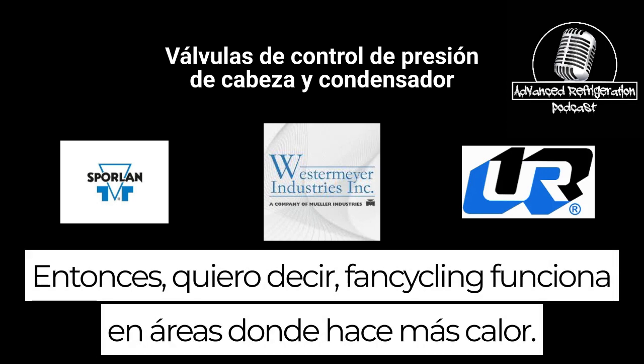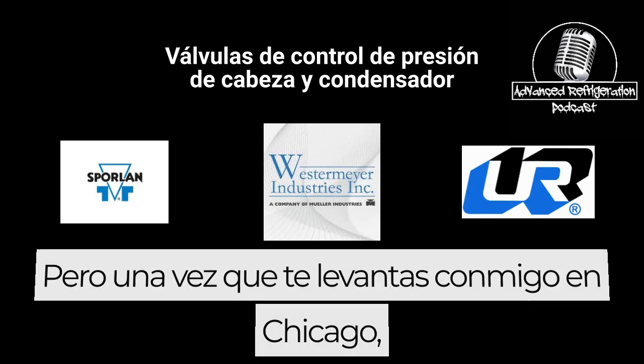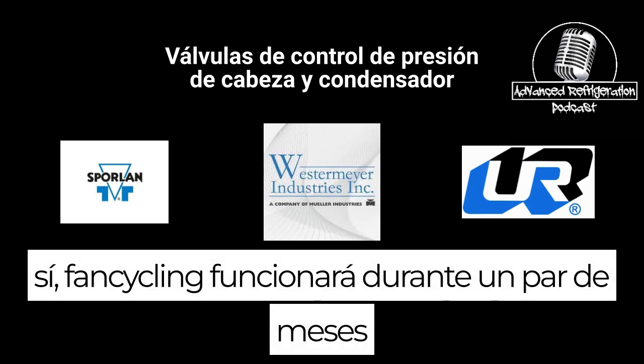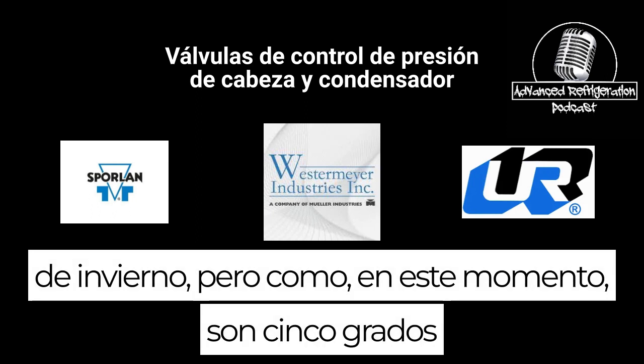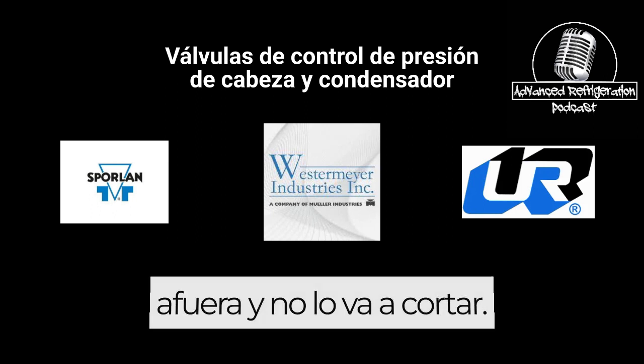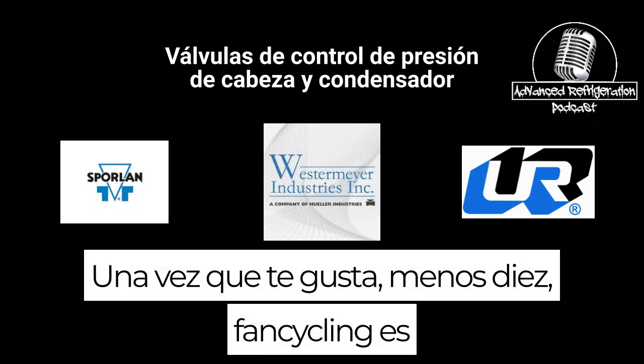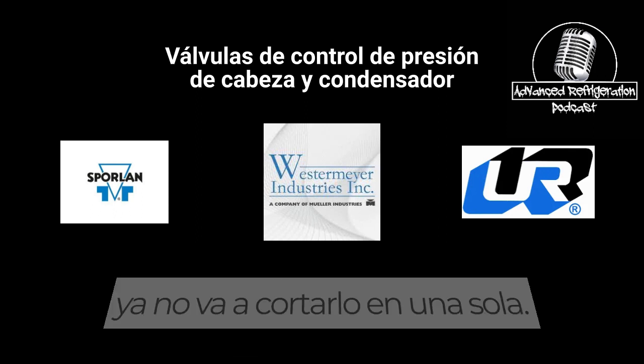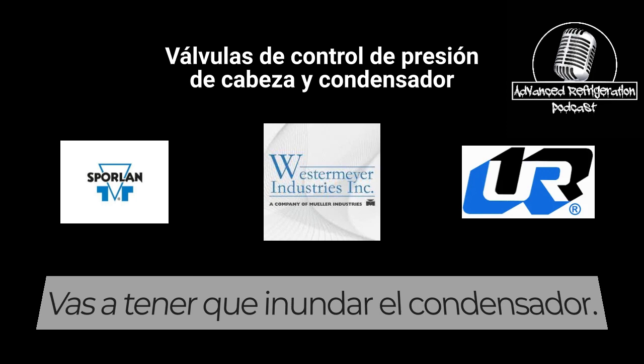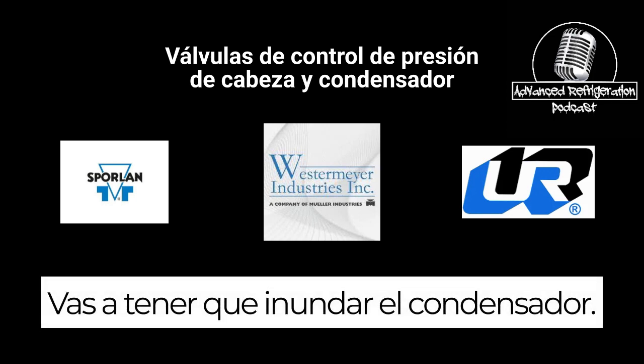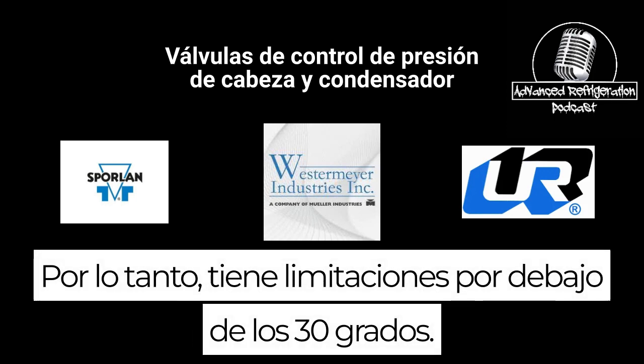So, I mean, fan cycling works in areas where it's warmer. But once you get up by me in Chicago, yeah, fan cycling will work for a couple months of winter. But like right now, it's 5 degrees outside and it's not going to cut it. Once you get down to like minus 10, fan cycling is no longer going to cut it on a single unit. I mean, you're going to have to flood the condenser. So it does have its limitations.